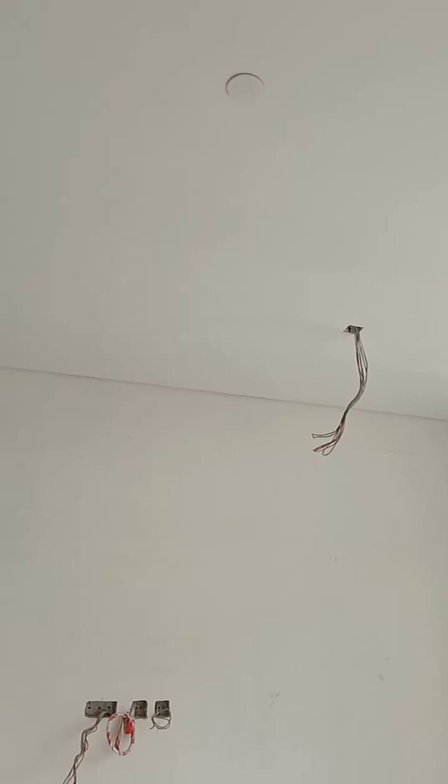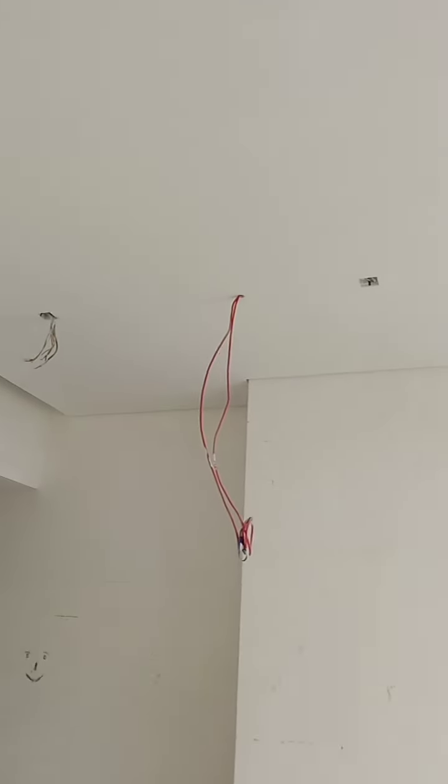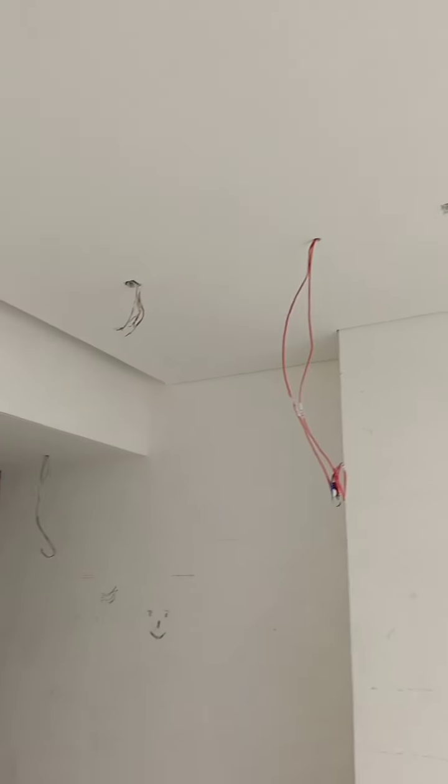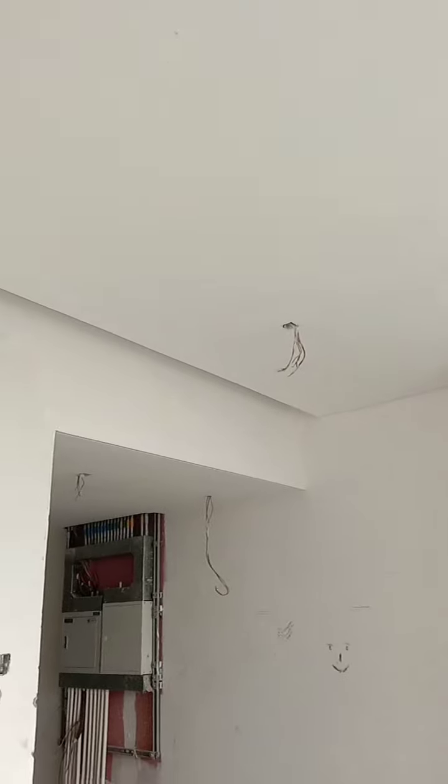So you notice above the false ceiling, all the exposed conduits are going to be GI conduit or the galvanized conduits. The PVC conduits are going to be embedded in the soffit. It's very important to understand as far as electrical installation works are concerned. So we've done the first fix, as well as the cable tray and trunkings, everything which is in the shop drawings, which we have to install on site. We've done all that as well.